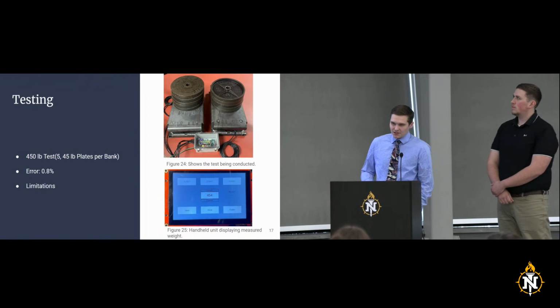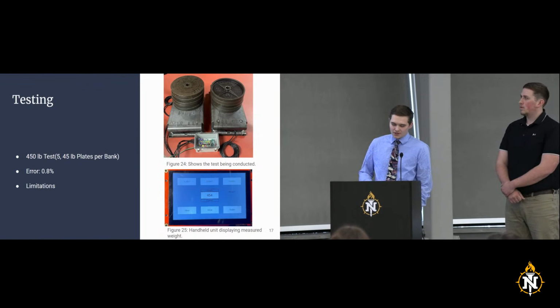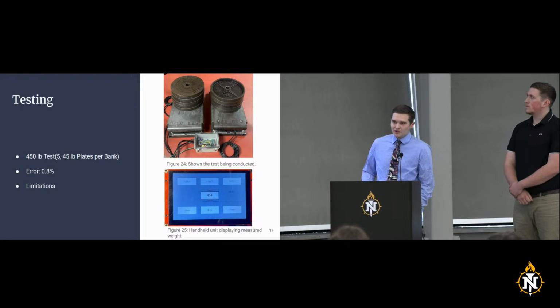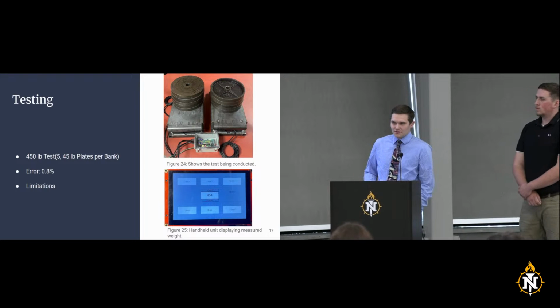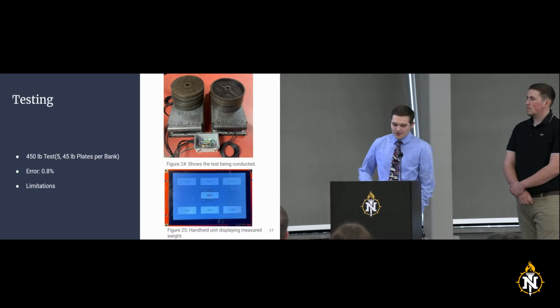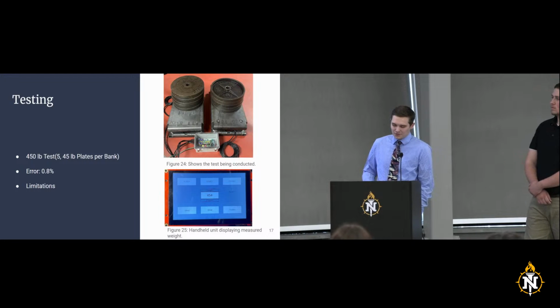Testing. So our first test we did was over at the PEEF. They allowed us to go over there and use their 45-pound weights and test the accuracy of our scale. So we put 5 45-pound plates on each bank of load cells. So that was a total of 450 pounds. And we read 454 pounds when that 450 was on there, which gives us about a 0.8% error, which is well below what we were expecting in the design and build of this whole thing.